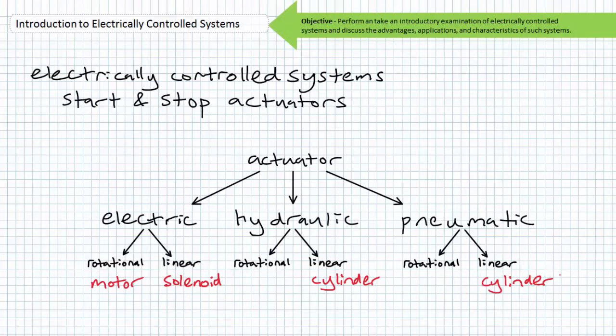For example, a rotating electrical motor can drive a conveyor belt in a straight line, and a hydraulic cylinder with a pivoting trunnion or clevis mount can tip or tilt an attached load. Numerous examples of actuators exist, and despite their differences of input energy or form of mechanical movement, they can all be electrically controlled. A magnetic contactor can start or stop a motor, and a solenoid-operated directional control valve can stop or start a hydraulic cylinder.